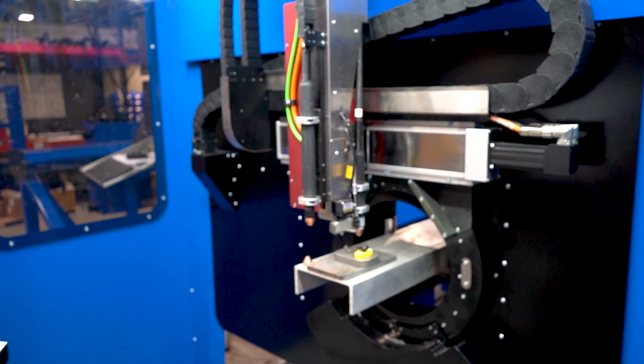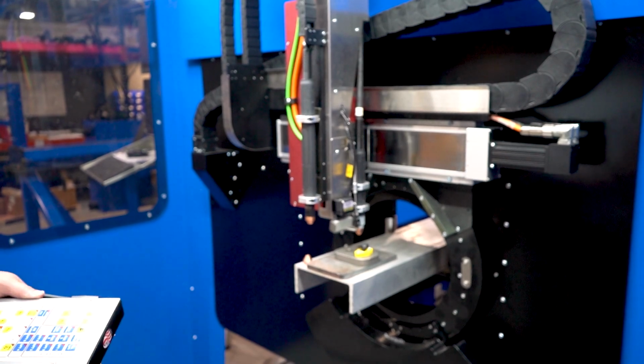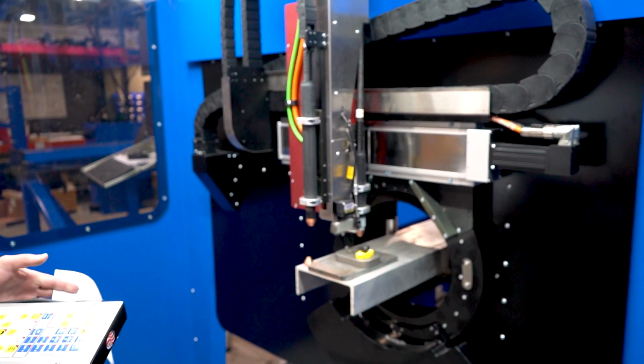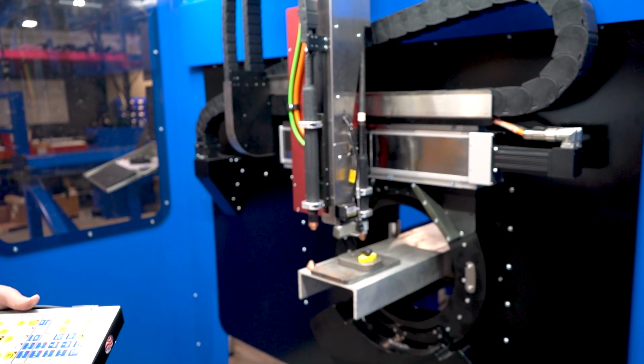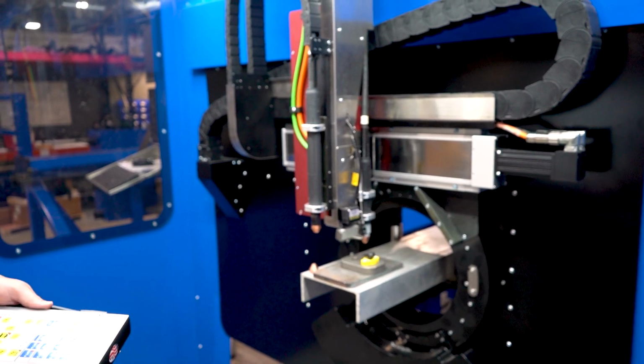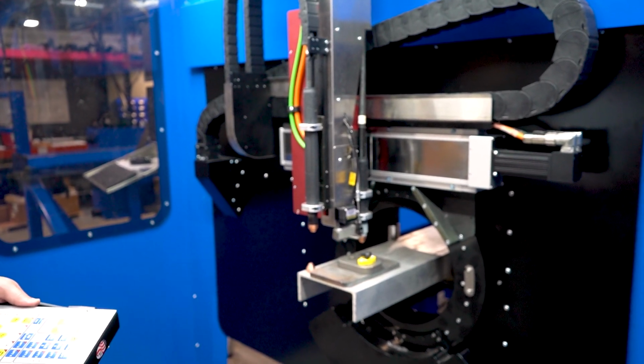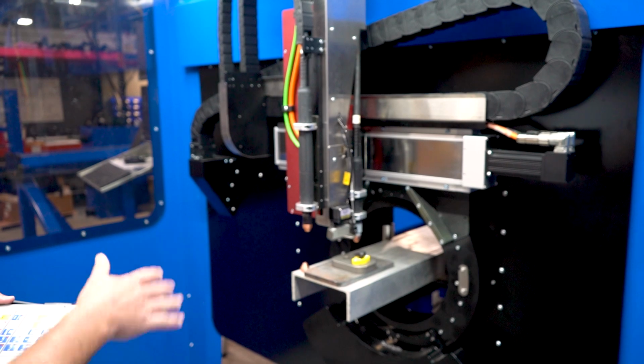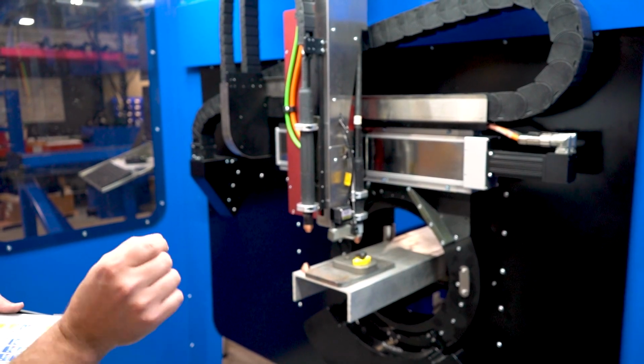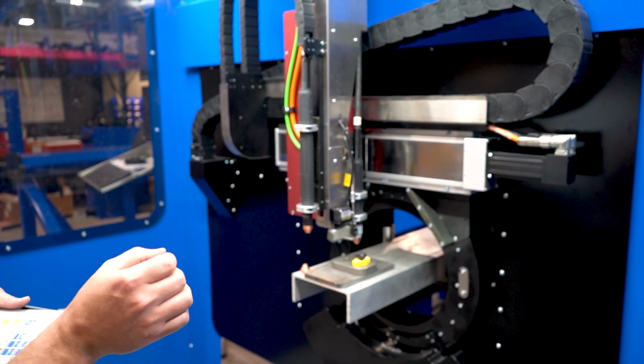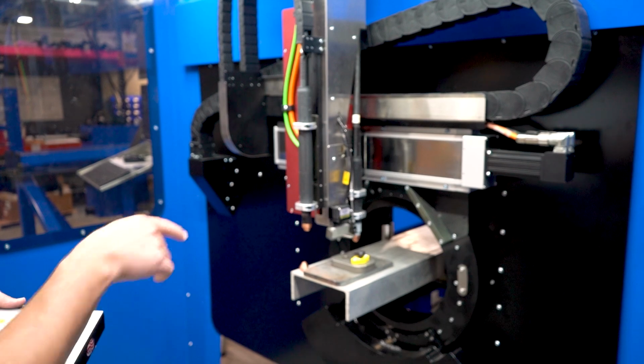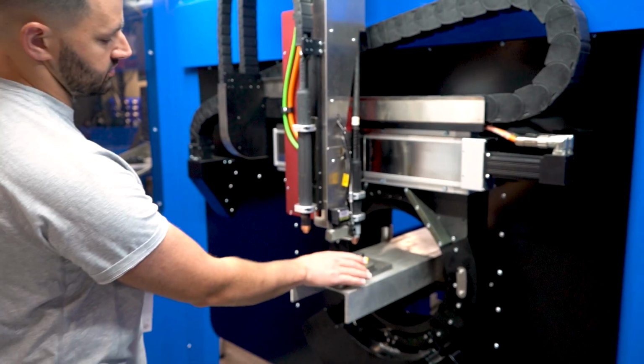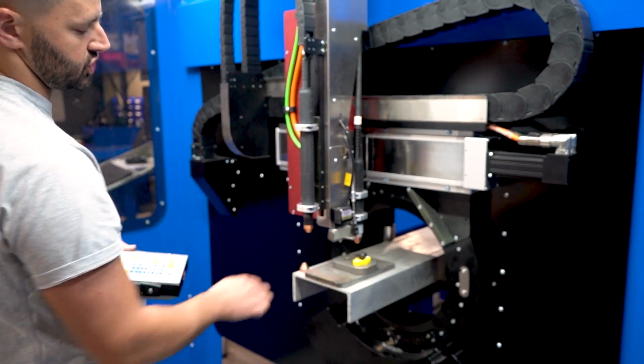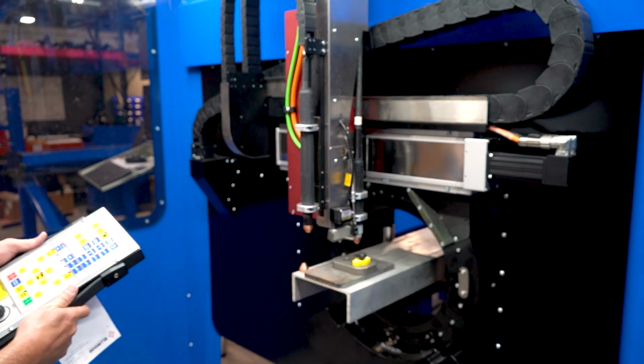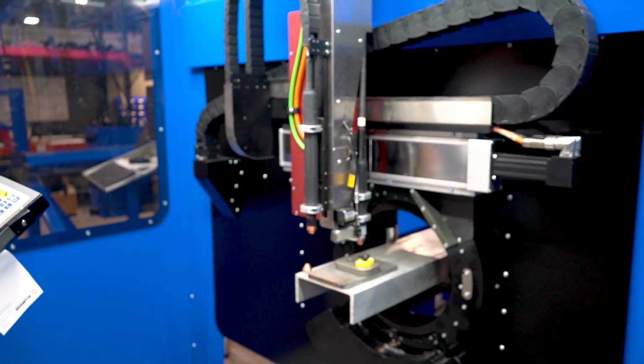This is what sets the nominal diameter of the actual laser beam. And then you'll see pop up on the screen, it'll say a number, usually close to 3/4 of an inch. As long as it's within plus or minus 0.003 of 3/4 of an inch, that's close enough for calibrating the laser, but more or less that'll tell you that it's repeating size of this calibration block. So this is a 3/4 inch diameter hole. So we'll go ahead and hit cycle start.